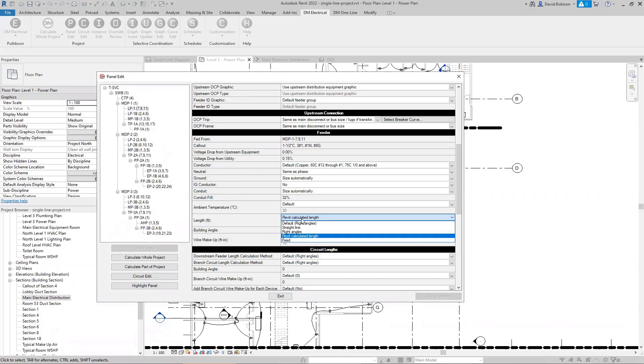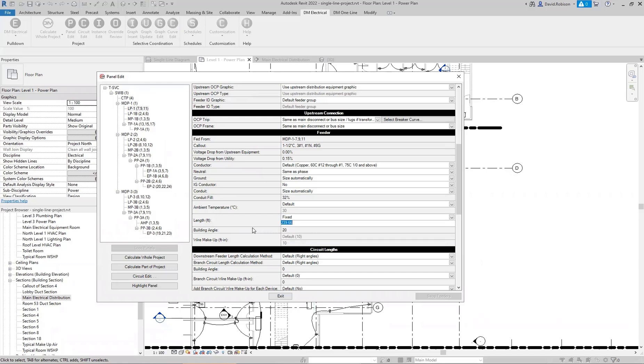The last option is fixed. You select this and type in a number. This is for when you know exactly how long the feeder is — say 250 feet — or when your panels aren't in their electrical rooms and the calculated lengths are wrong, so you just tell the software what the length is.